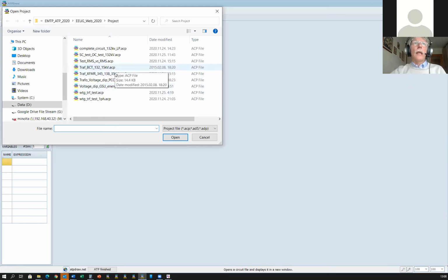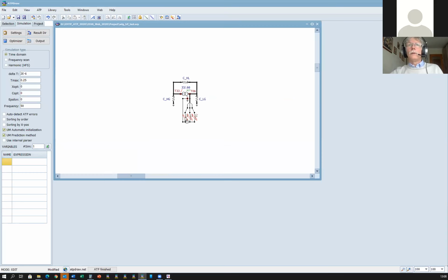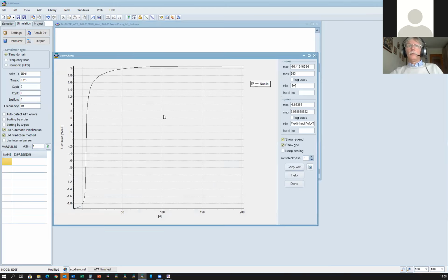You can scale this transformer model, the working one, easily, because if you know the hysteretic curve, it is tested, it works as you expected, you can keep this curve forever, because you can rate this one to a transformer with different power rate, with different voltage level.